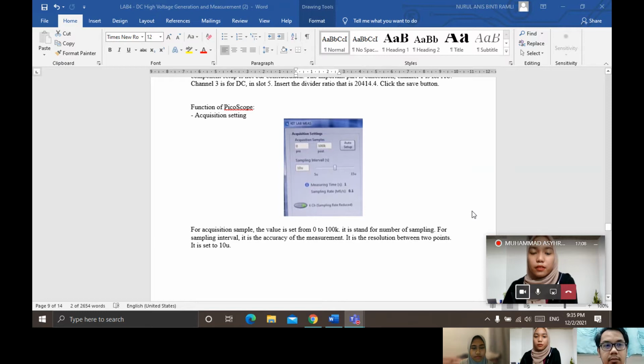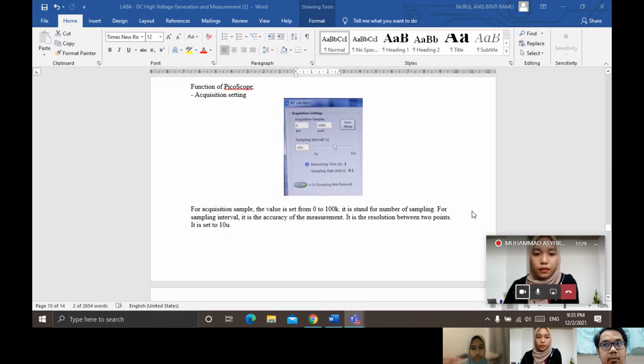Okay, this is the function of the picoscope. The first one is the acquisition setting. For acquisition sample, the value is set from 0 to 100K. It stands for the number of samplings. The sampling interval is the accuracy of the measurement. It is the resolution between 2 points. It is set to 10 micro.